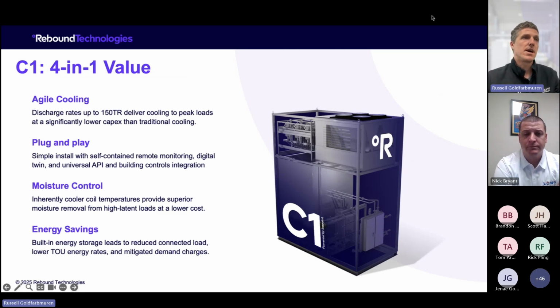The product is an ice storage system, and I think we're all probably somewhat familiar with ice storage. This is quite a bit different from a technology standpoint. I'll get into that in a second, but I want to highlight the value, right off the bat. So the number one value of the product is what we call agile cooling. This is the ability to be both asynchronous and asymmetric. I'll define both those terms. Asynchronous is what we're familiar with in ice storage. We buy 300 kilowatt hours of cooling in the middle of the night, and we use it in the middle of the day. And our product does that just like any ice storage system.